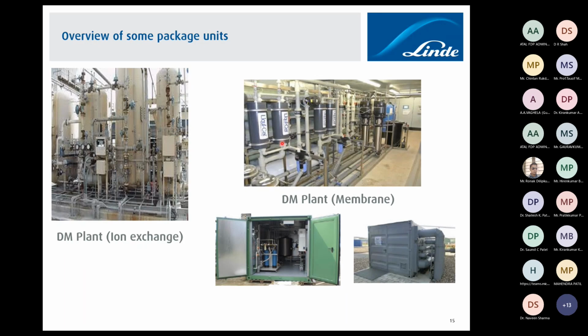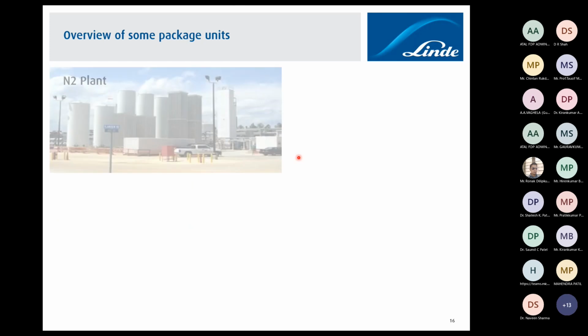And nowadays, a modern trend is membrane based technology, which is also available and which absorbs target cations and target anions. So this is how membrane based technology works. In Europe, where the temperature is quite low and you cannot use plastic piping and plastic membrane cells because the ambient temperature is below zero, you will find containerized plants. Everything fits into a 40 feet container, sometimes 20 feet containers, and we only have to connect some piping from outside along with the insulation. So these are the different variants available for the demineralization unit.